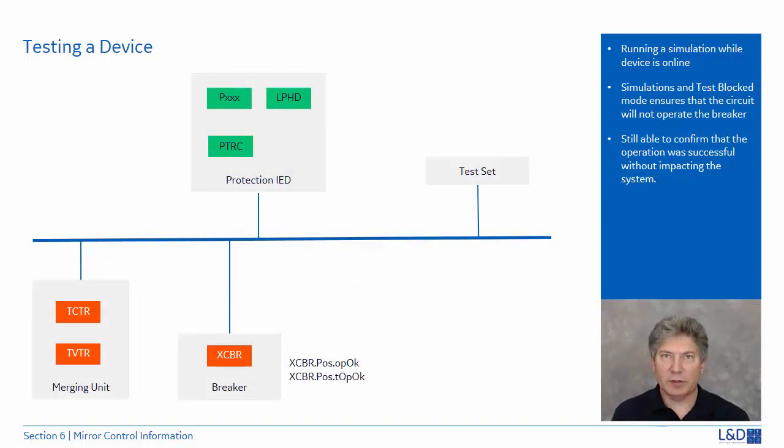Let's review how it's possible to test a device that is connected to the system. In our example, we want to test the performance of a main protection that receives sample values from a merging unit and trips the breaker through a breaker IED over a process bus.